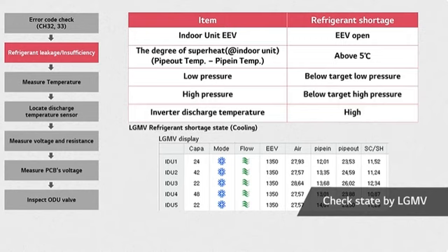Low refrigerant volume may cause excessive discharge temperature. There are two possible causes for lack of refrigerant. Maybe the right amount was not charged into the system from the very beginning, or there is a leakage in the piping. Check the brazing and flare connections of the air conditioner.